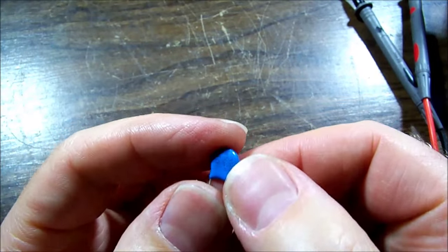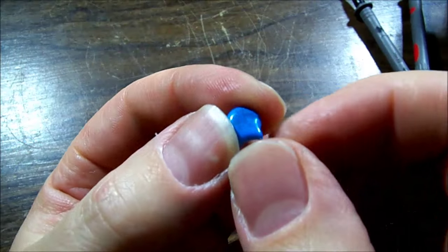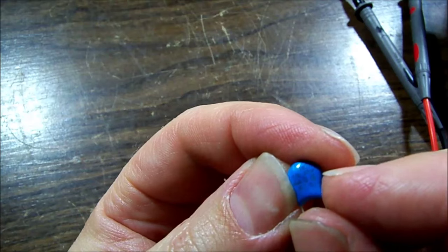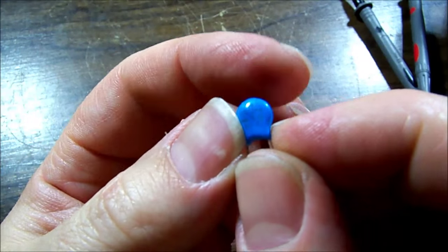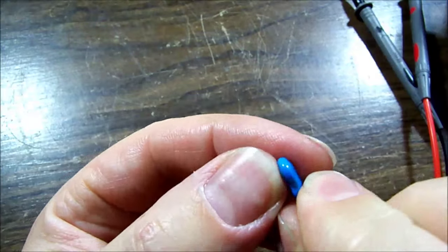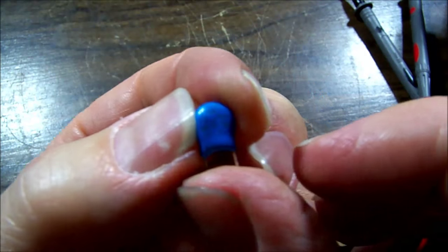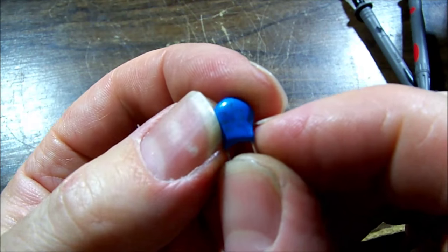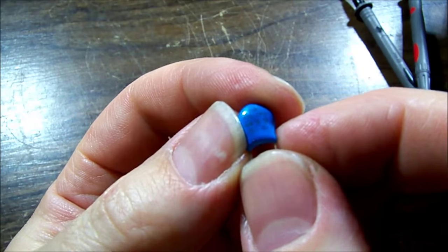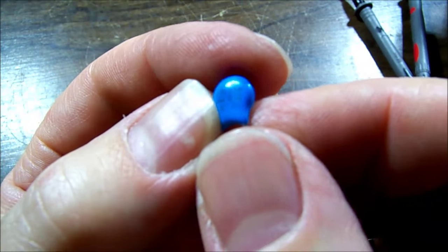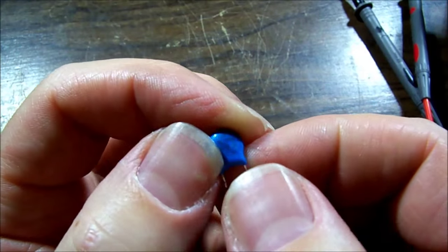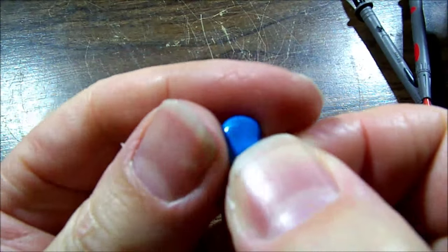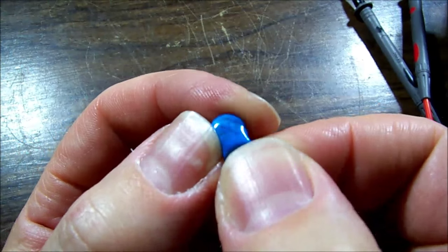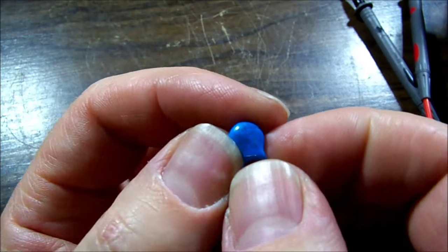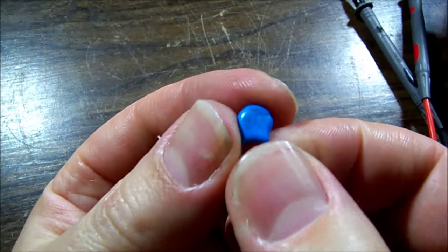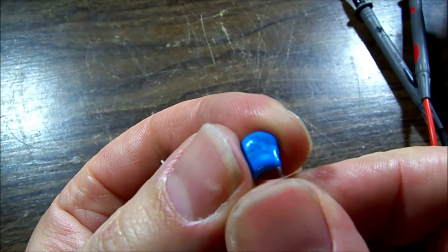Not a short, but became a low resistance, which was upsetting the signaling on the line. Hang on a minute, I hear you saying, that doesn't sound right, and you might be right. On further investigation, this is a MOV, metal oxide varistor, which should be a much higher resistance than that. So still along the same lines as where we were going with it, not a capacitor. In hindsight, I suppose a capacitor like this would have been just open-circuited by a high voltage surge, but this one has done its dash.